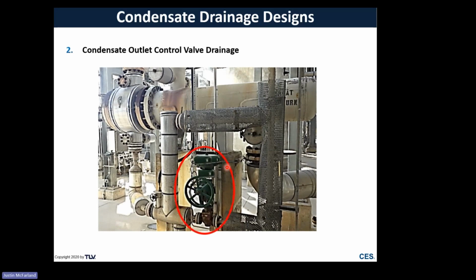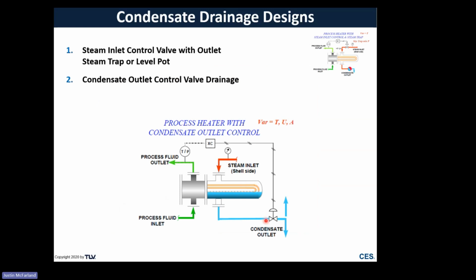Next one, a very, very common one I see in heavy industry, is the outlet control valve. So this is actually designed with the intention to back up condensate inside the process heater. But inevitably, what we often see is that steam is oftentimes blowing through. And I'll explain that here in just a second. So really, really simple system. Instead of an inlet modulating control valve, we have an outlet side modulating control valve. The reason this is so common is because the upfront cost of this type of system is very, very low. Instead of having two devices, an inlet valve and some sort of drainage device on the outlet side, you have just one valve on the outlet side, which is probably going to be quite a bit smaller than an inlet side valve, just due to the differences in specific volume of steam compared to water. So lower upfront cost, but there's some big drawbacks and reliability issues over time.